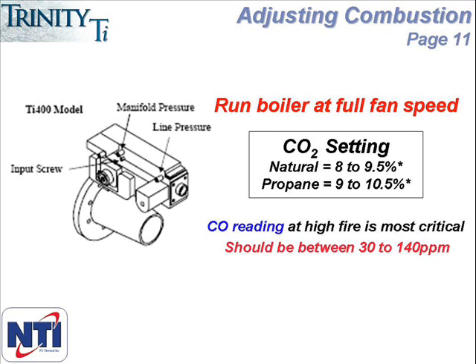When you look at the gas valve, you'll see two ports and the line pressure port is the one toward the right-hand side of the valve. The port over the input screw is the manifold port and doesn't need to be used. The input screw works a little differently than the other models in that it isn't a needle valve but a geared ball valve with a 4 to 1 ratio.